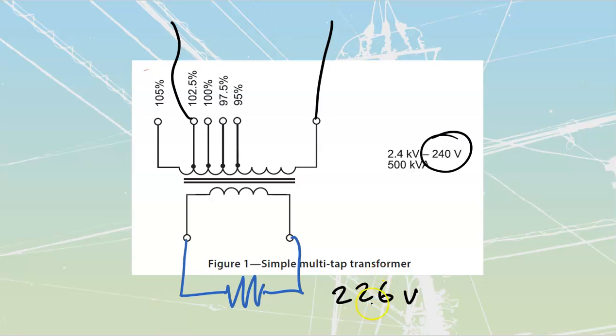But right now, we're getting 226 volts out of this thing, and when I open up the transformer plate and take a look inside there, I see that this thing is on the 102.5% tap. So what I need to do is figure out how many volts I have incoming over here. Once I know that incoming voltage, then I'm going to be able to figure out my percent tap off of it. Here's how we figure out that incoming voltage.